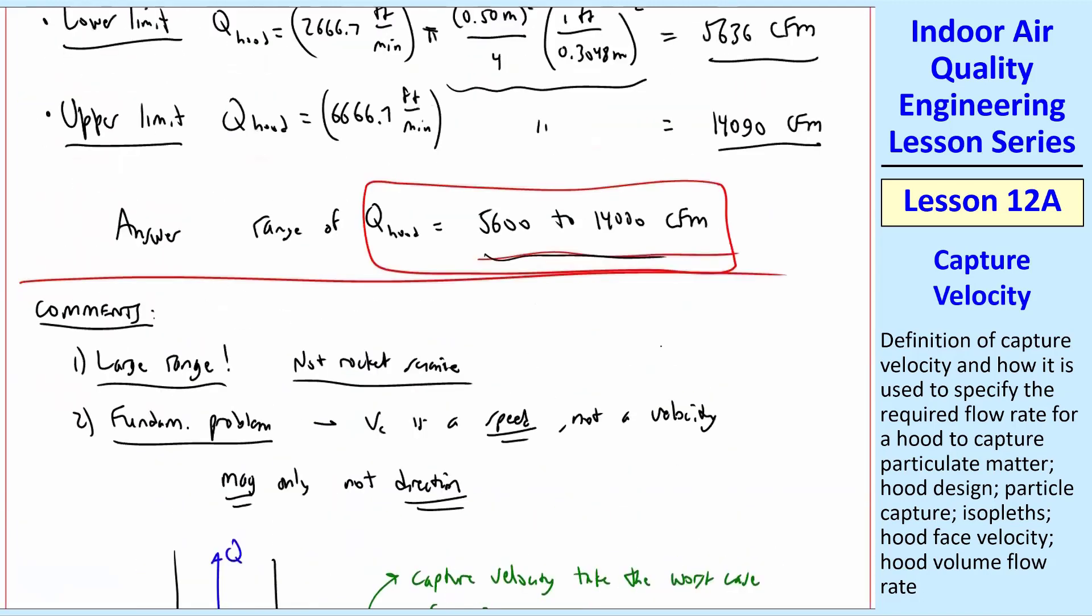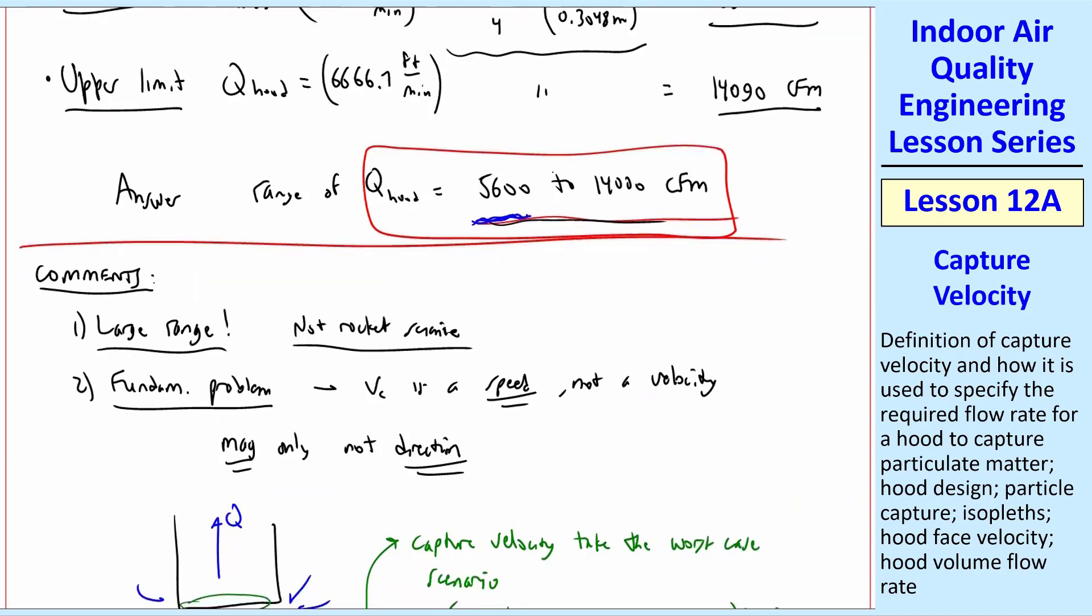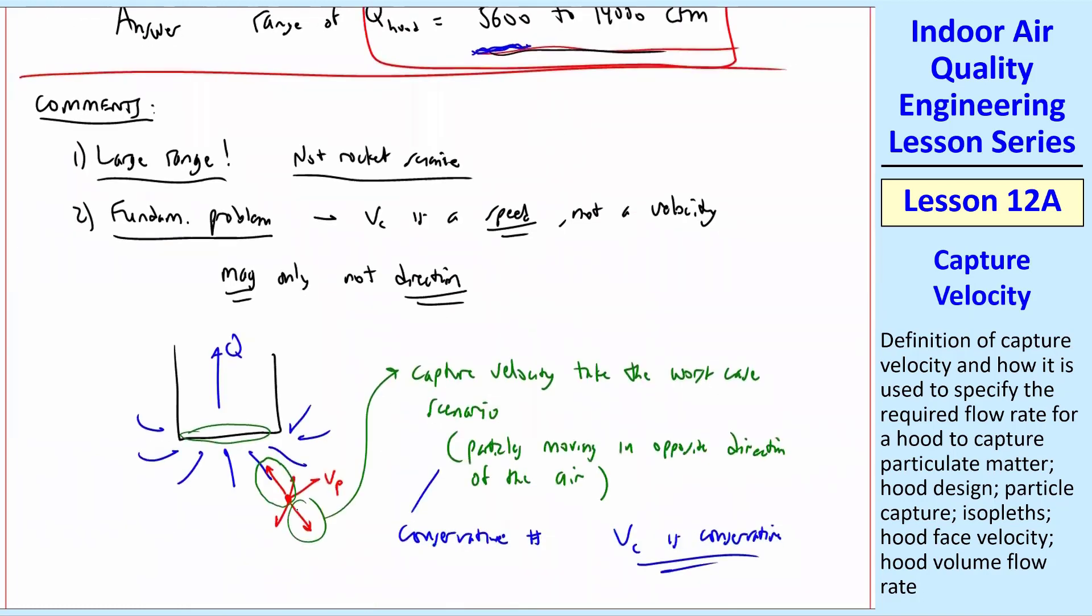So in other words, it's particles moving in the opposite direction of the air coming into the hood. So this is a conservative number. So VC is a conservative value. We're saying in this case, you had nice room conditions and low toxicity, you would say 5,600 CFM. That's only for a particle that happens to be moving away in the exact opposite direction of the flow. It may not be if you're painting or welding or something. You may have particles flying around. It may not always be going away, obviously.